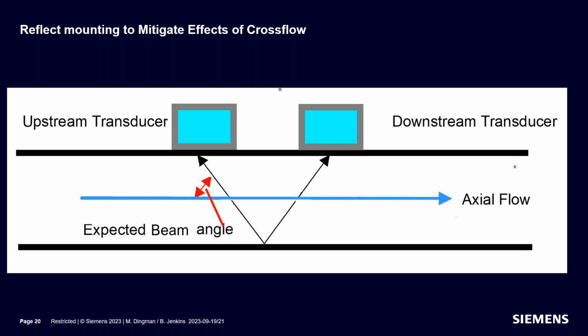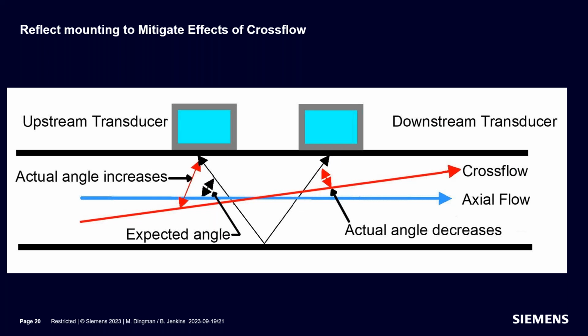So this is why we want a straight run of pipe, because if you have a long straight run, the flow is axial. It gets back to becoming axial after a certain number of pipe diameters, and it's parallel to the pipe walls as you would expect. But if you're relatively close to pipe anomalies, you can see crossflow conditions. So here's a crossflow condition. And this is a little dramatic, but the flow is traveling at an angle relative to the pipe walls because it came around an elbow, and now it's not propagating axially down the pipe.